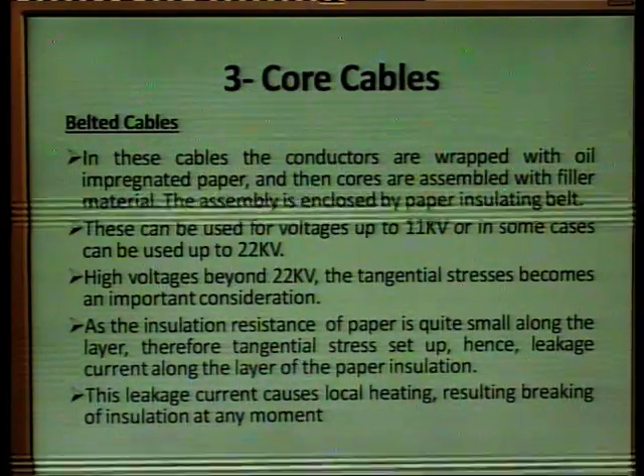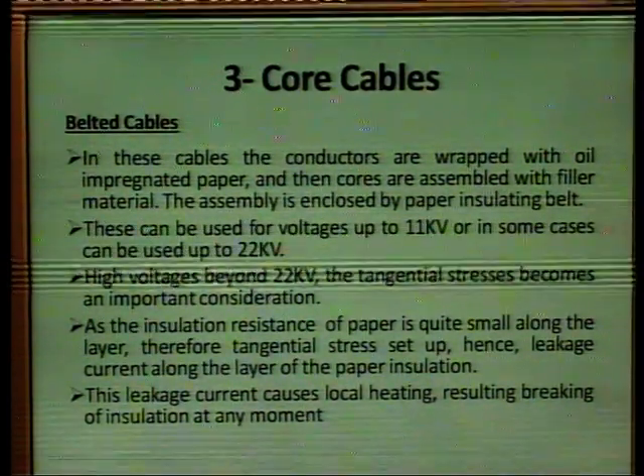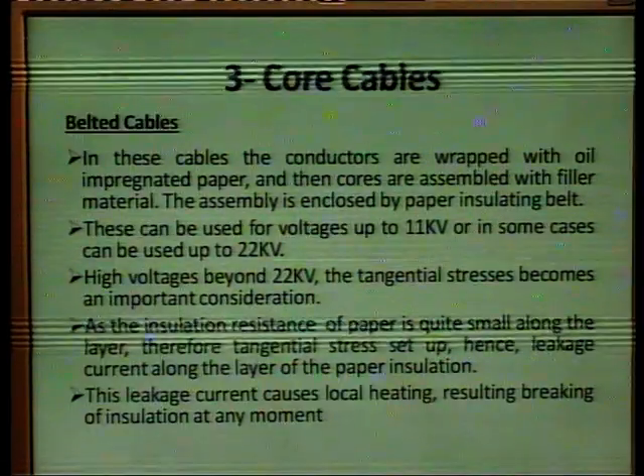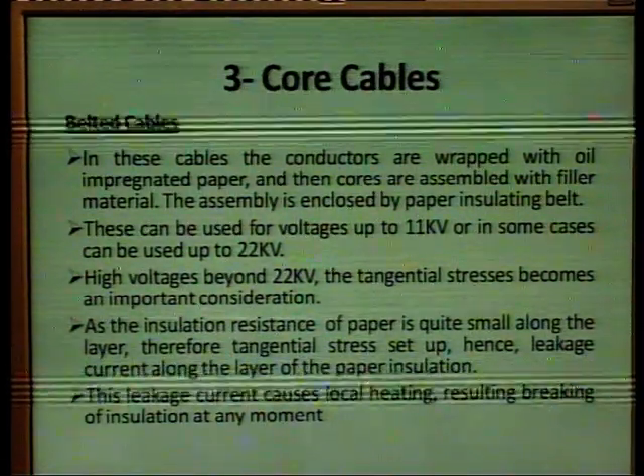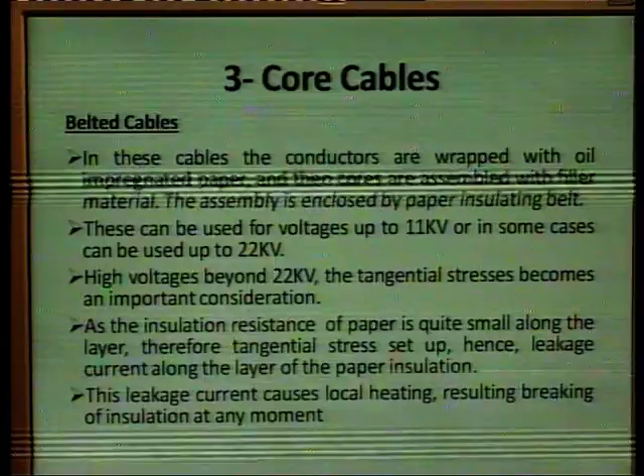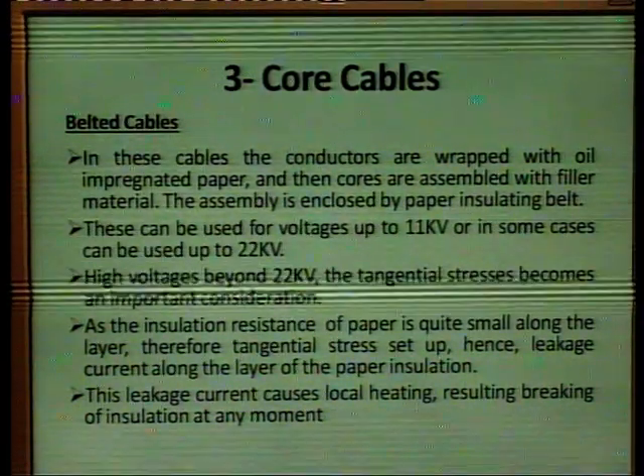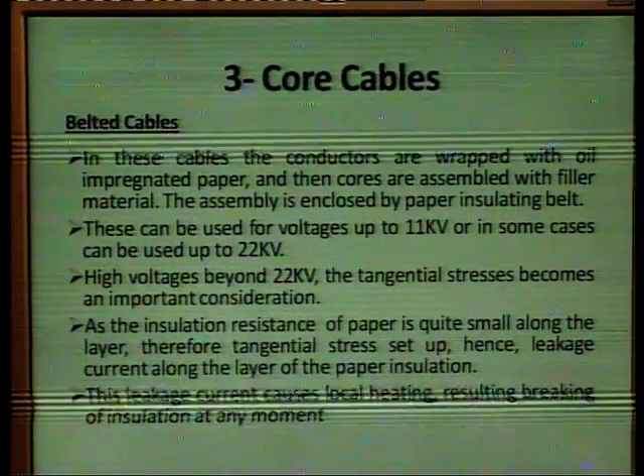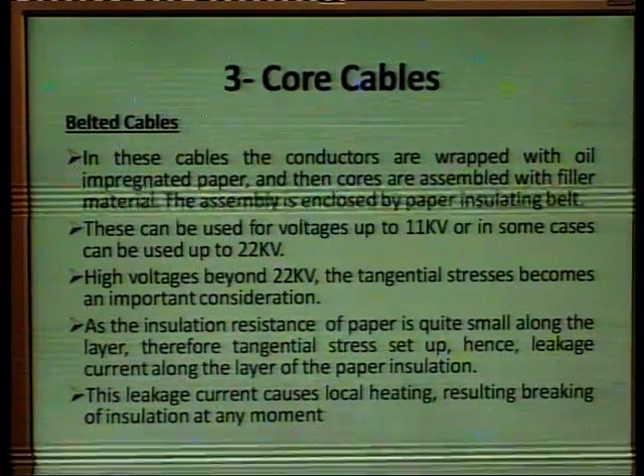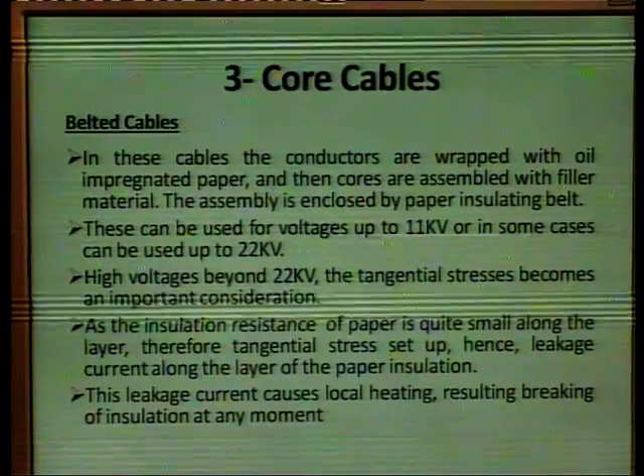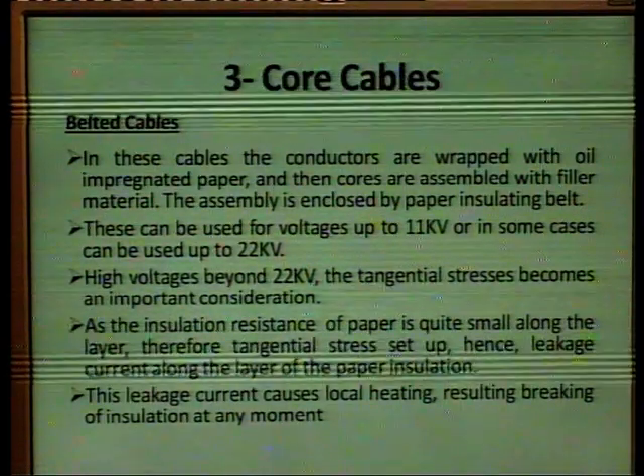For high voltages beyond 22 kV, the tangential stresses become an important consideration, as the insulation resistance of the paper is small along the layer. Therefore the tangential stresses set up a leakage current along the layer of the paper insulation, and this leakage current causes local heating, resulting in breaking of the insulation at any moment.